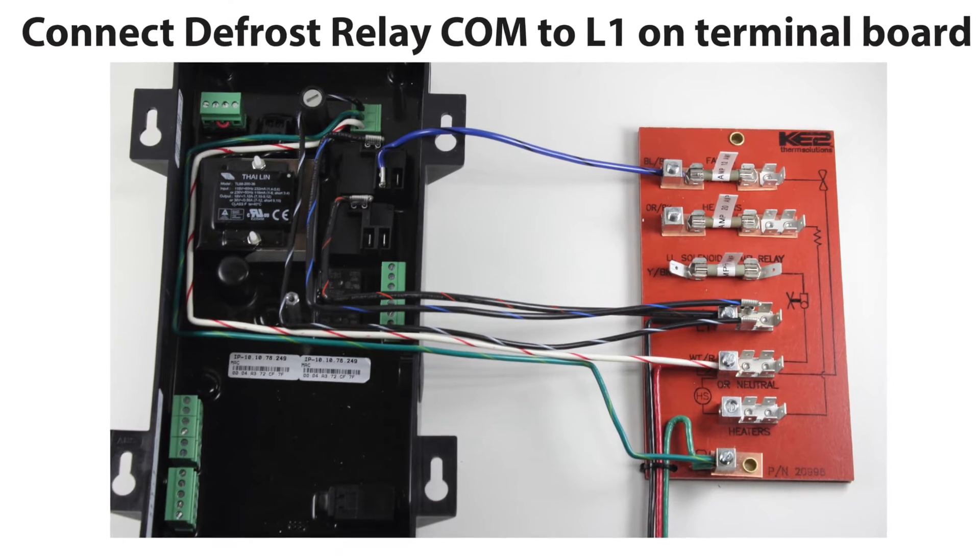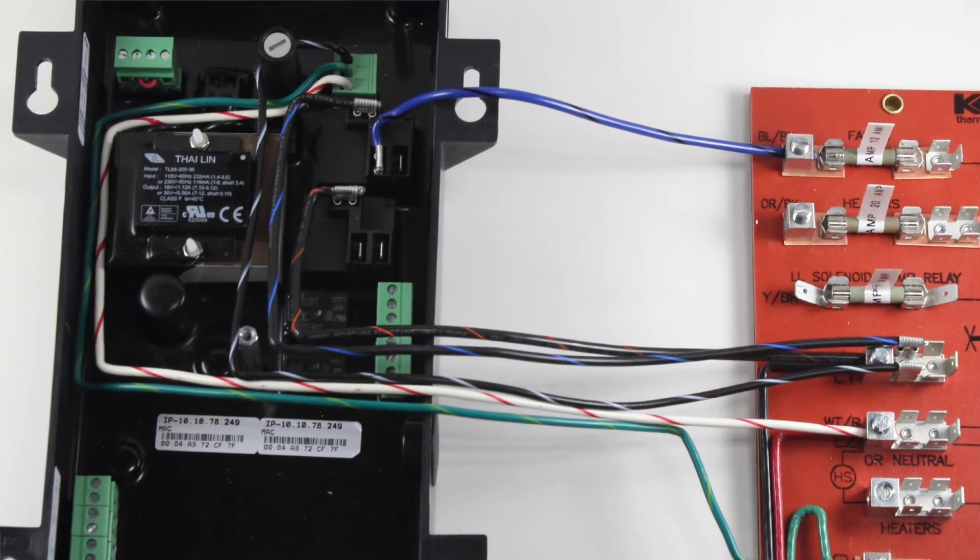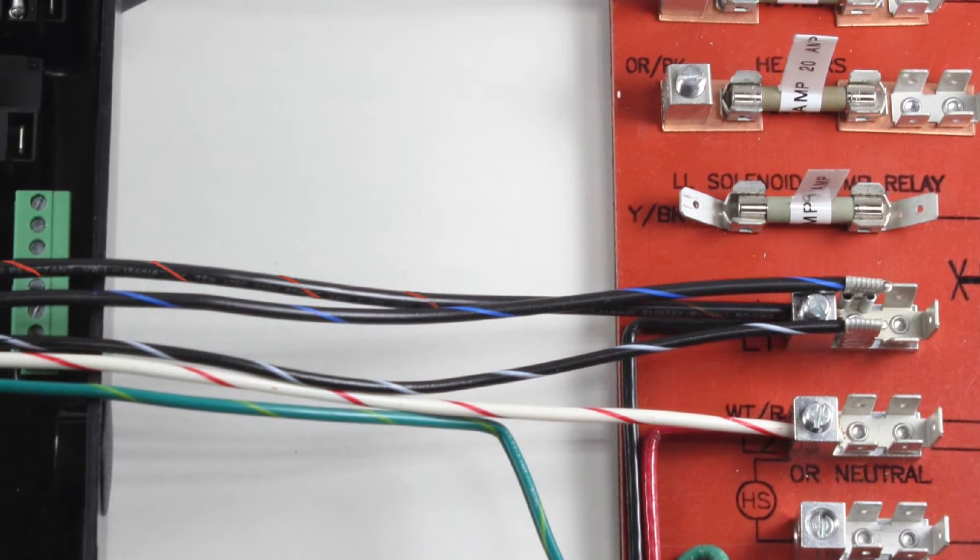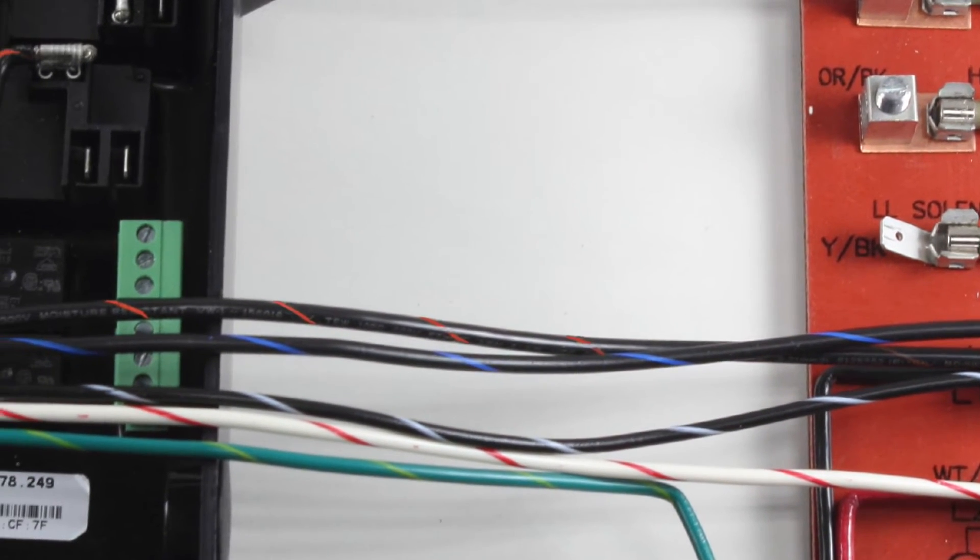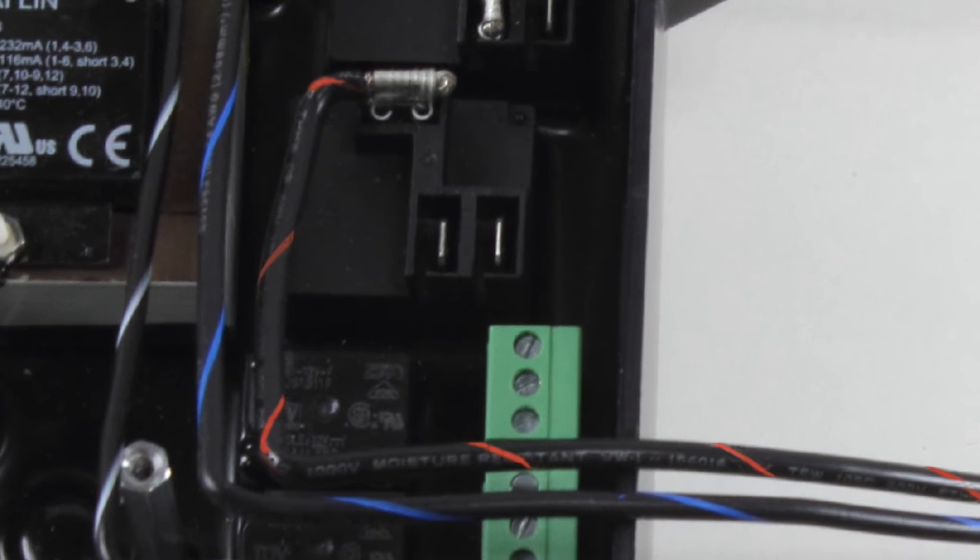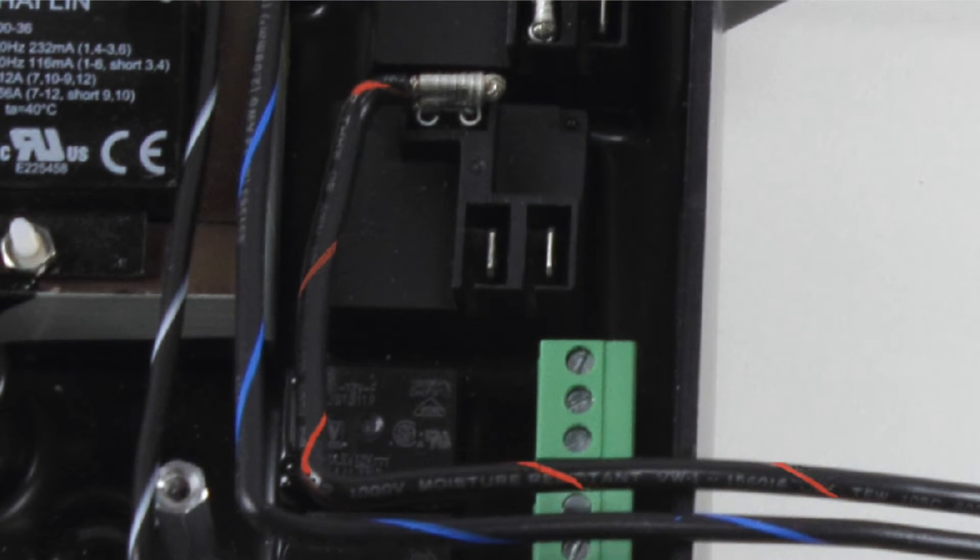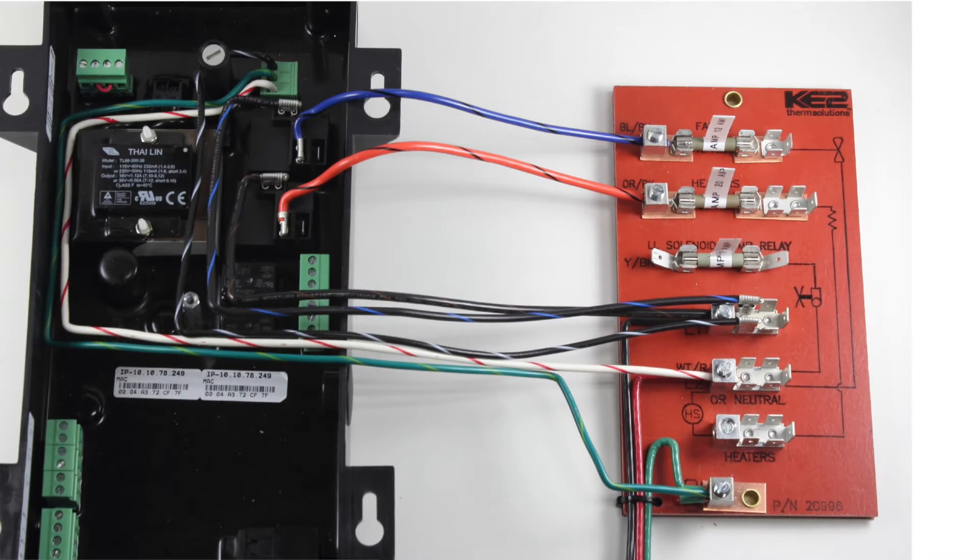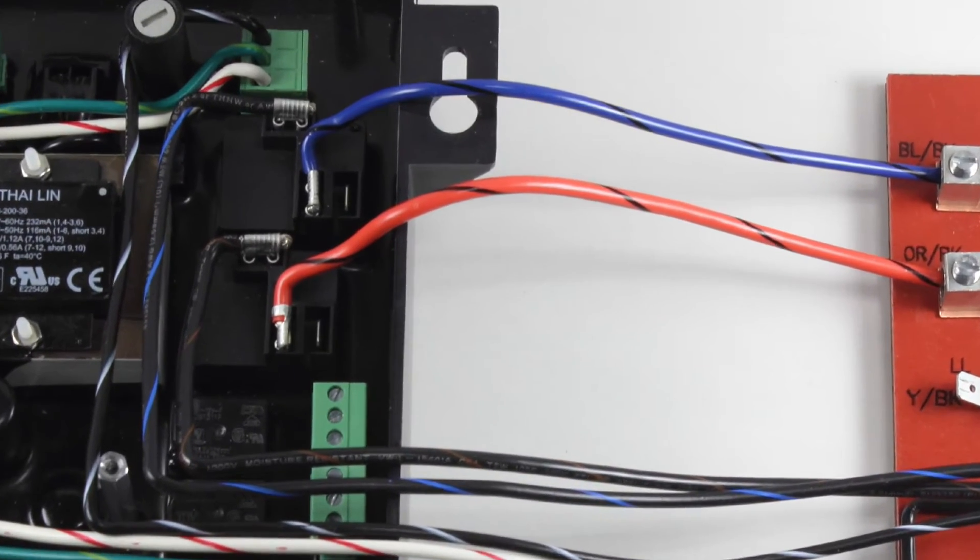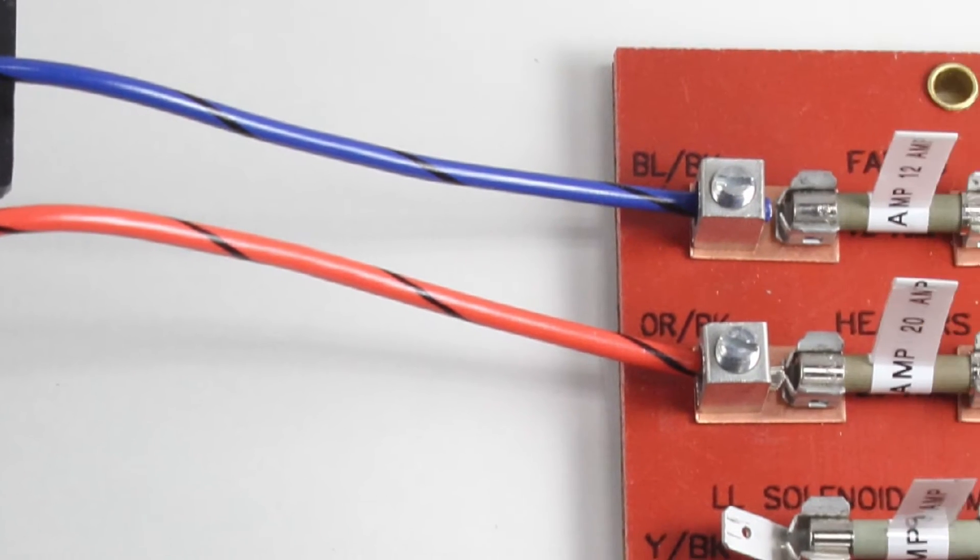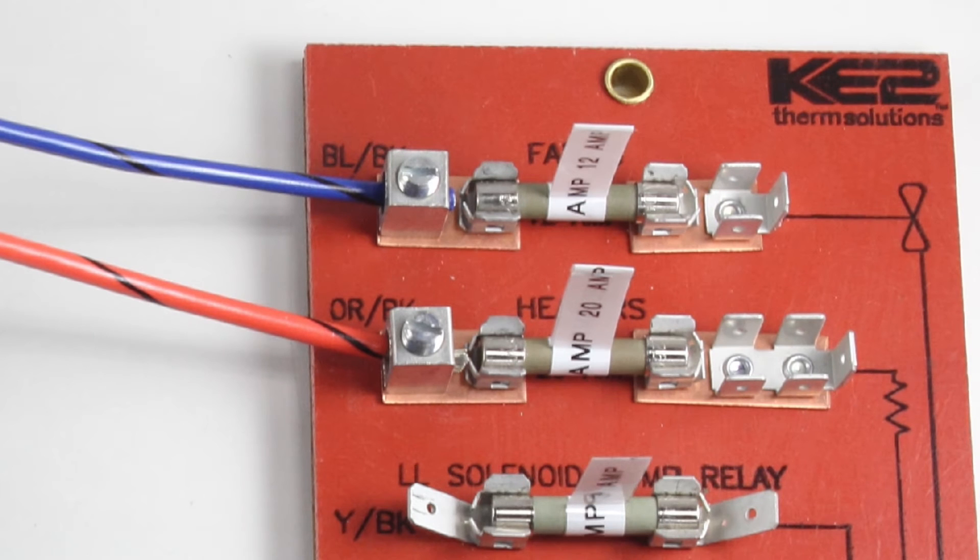Next, the defrost relay dry contact needs power provided to the common terminal. Connect line 1 on the terminal board using the black with orange stripe. Wire to the common on the defrost relay as shown. Connect from the defrost relay normally open set of contacts using the orange with black stripe wire to the orange/black location as shown on the terminal board.